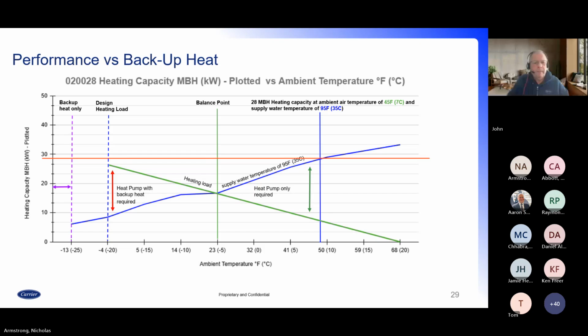Okay, next slide. So with this slide here, we're going to show when do we need backup heat, and there's two ways we can do backup heat for the heat pump. We can do backup heat either with the built-in electric coils that are in the indoor unit, as we talked about previously, and it adds either 20,000 or 30,000, depending on the size of the heat pump you have, supplement heat to the unit, and we can use the backup coils as a true bivalent type output. In other words, the heat pump and the electric coils will work in tandem together.